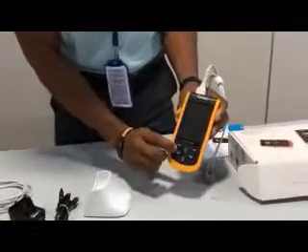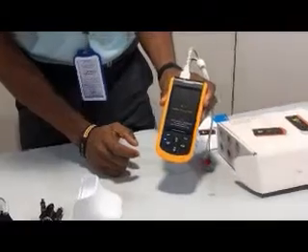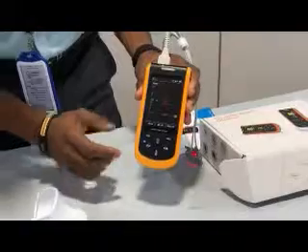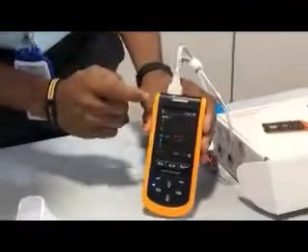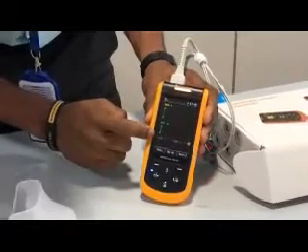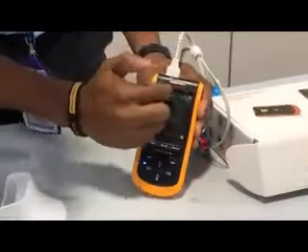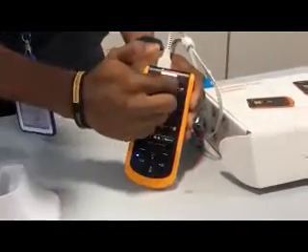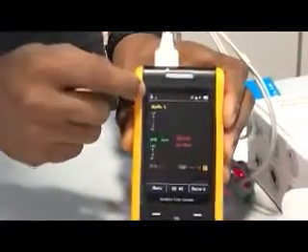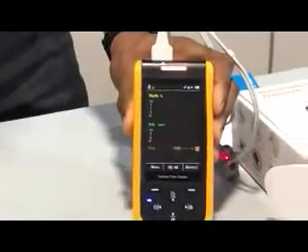I turn on this device here on this button — the power button. Just press it for a few seconds and it comes on. As you can see, there is a display showing SPO2, pulse rate, perfusion index, menu, time, record, and temperature. And there is the auto-rotate and battery bar. Also on this side, you can see a baby icon, telling you that this device is on neonate mode. It has a neonate mode and an adult mode.